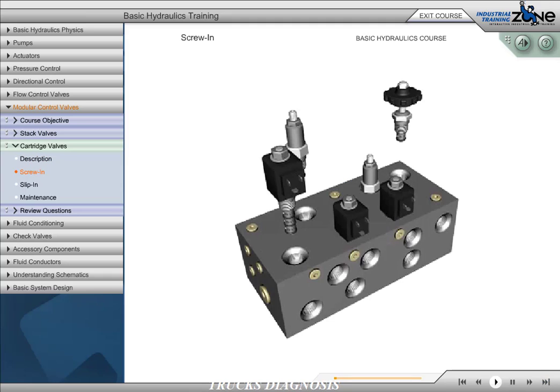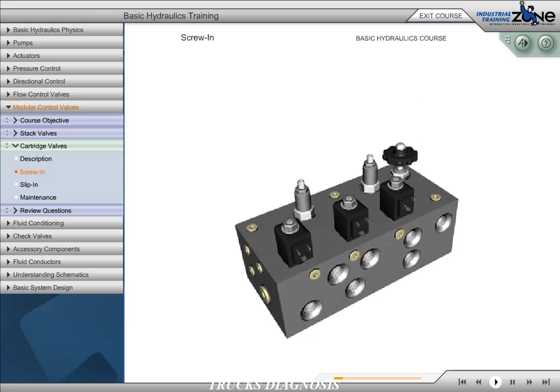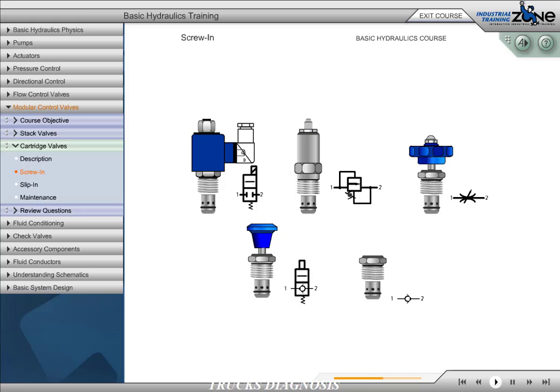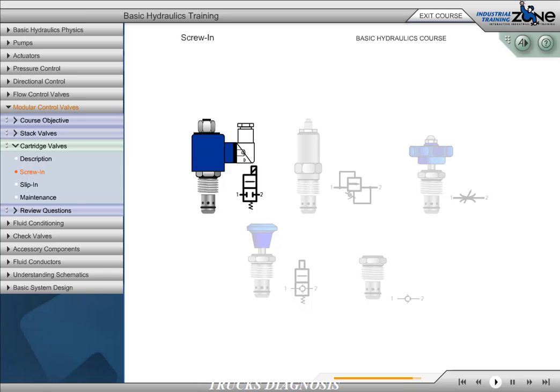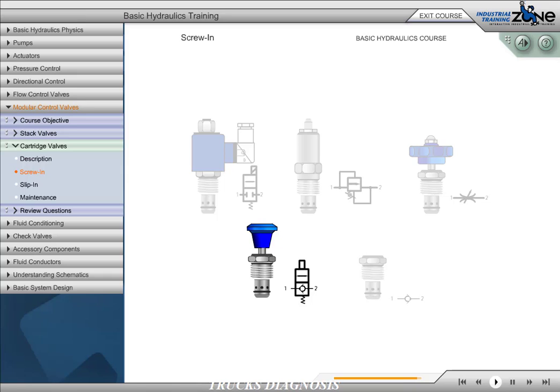The screw-in style cartridge valve uses a threaded base to secure the valve in the cavity. Screw-in cartridges use either a spool, poppet, or ball valve element. The spool element can be used for two-way, three-way, or four-way flow functions, while the poppet and ball elements provide for only a two-way flow function. Screw-in cartridge valves are typically used in low-flow systems where the flow is 35 gallons per minute or less. Available configurations include check valve, relief valve, needle valve, solenoid operated directional control valve, and manually operated directional control valves.